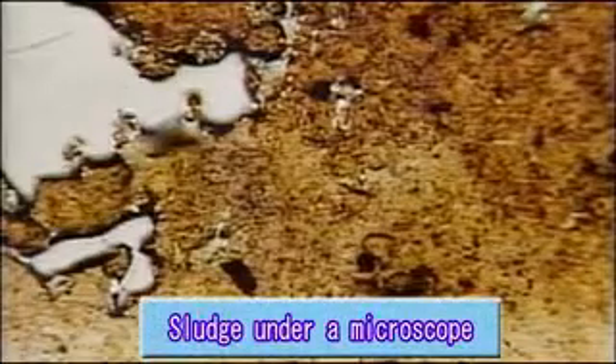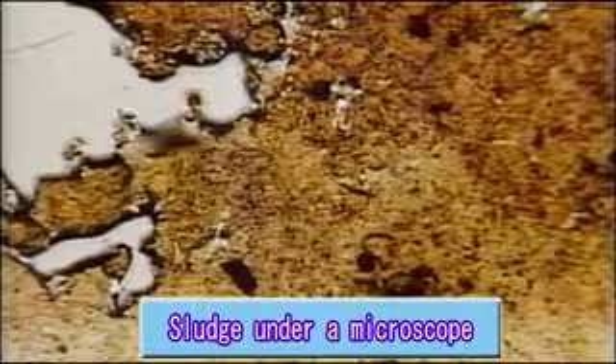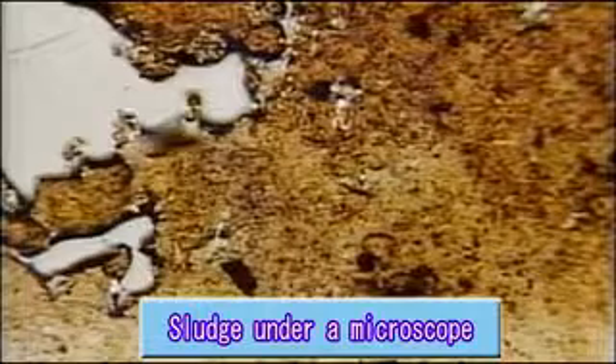This photograph shows the sludge seen under a microscope. We see that it is composed almost completely of degenerated oil material that allows light to pass through, and only trace amounts of solid particles such as metal or dirt that do not allow light to pass through.